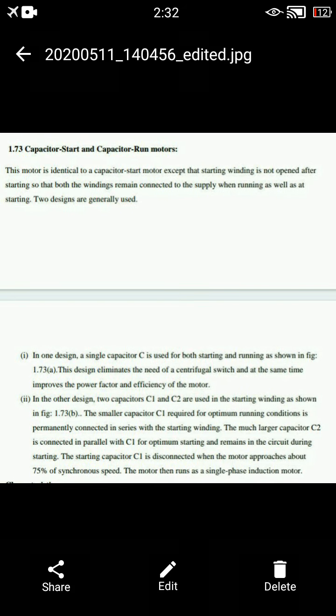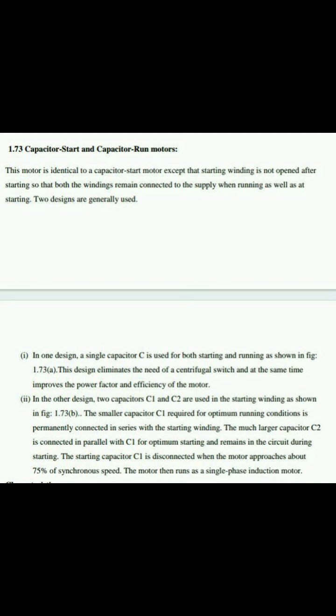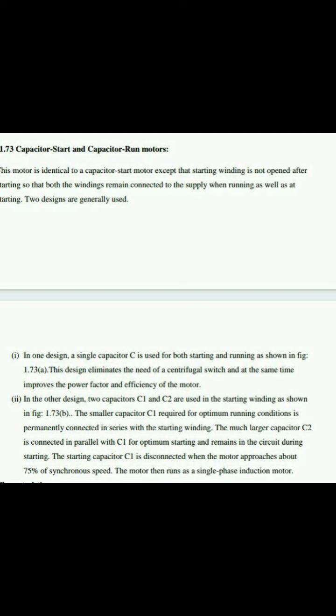There are basically two designs. In the first design, a single capacitor C is used for both starting and running conditions. This design eliminates the need for a centrifugal switch and improves power factor and efficiency. In the second design, capacitors C1 and C2 are used in the starting winding. The smaller capacitor C1, required for optimum running conditions, is permanently connected in series with the starting winding. The much larger capacitor C2 is connected in parallel with C1 for optimum starting.